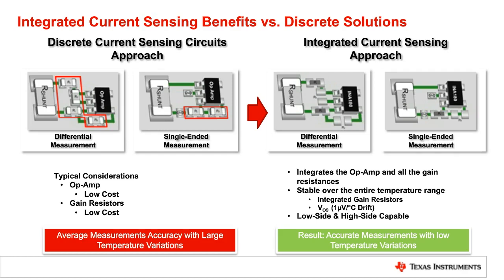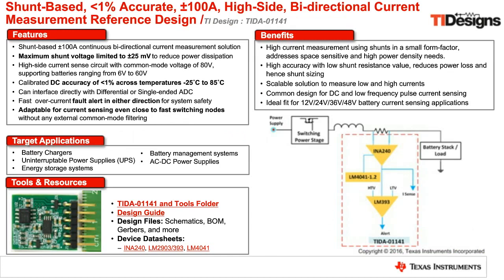If you're interested in seeing some of the performance characteristics of these devices, we have a specific TI design, TIDA 01141, which uses an INA240 paired with an LM393 comparator. This particular design is specified for plus or minus 100 amps and is capable of less than 1% error across a wide temperature range.